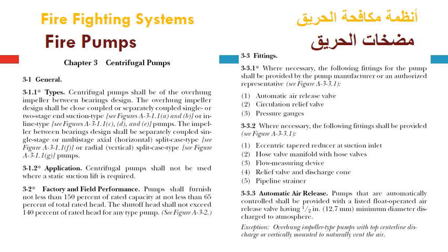1. Eccentric tapered reducer at the suction inlet to adapt the suction line diameter to the suction flange diameter according to the manufacturer design. 2. Hose valve manifold with hose valves to meter and test the pump performance and its flow rates, according to each hose valve rating and the amount of flow to be discharged through it. 3. Flow measuring device to monitor and meter the flow discharged from each pump separately. 4. Relief valve and discharge cone. The discharge cone will adapt the discharge flange diameter to the designed diameter of the discharge line for each pump.